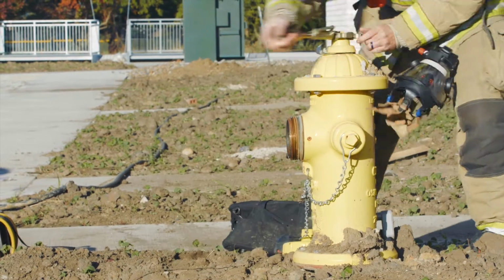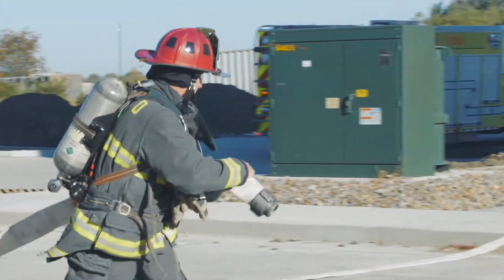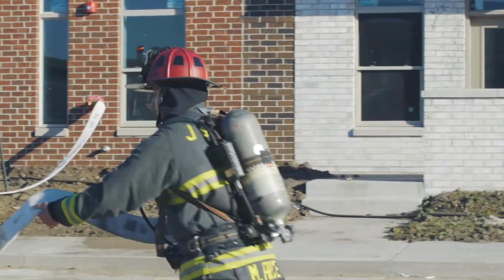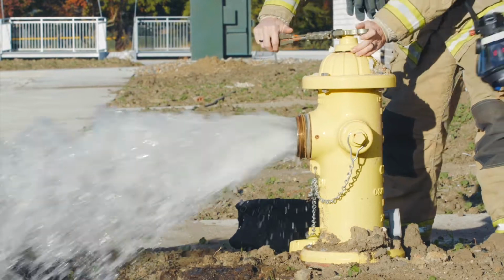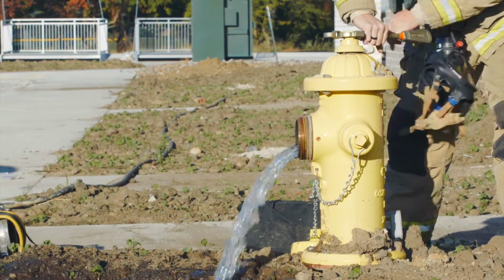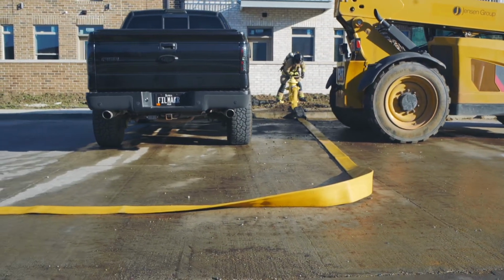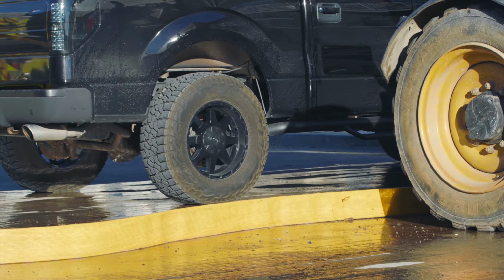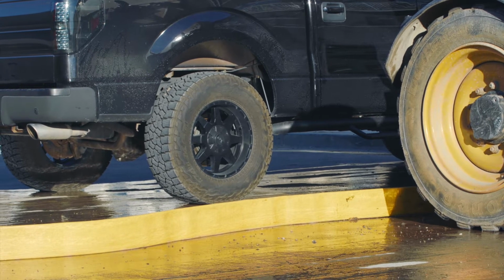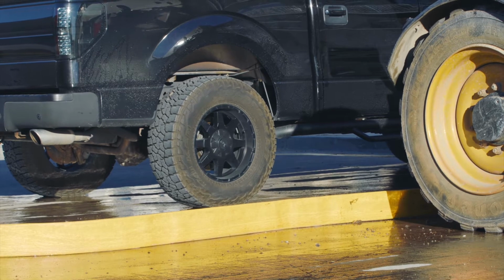of an approved connection. When fire hydrants and department connections are placed, designers should allow unobstructed access to hydrants and connections. There are typically two types of obstructions that exist on a finished site. The first is vehicle parking. Vehicles should never be allowed directly in front of a hydrant or fire connection. This condition is addressed in two separate code sections.